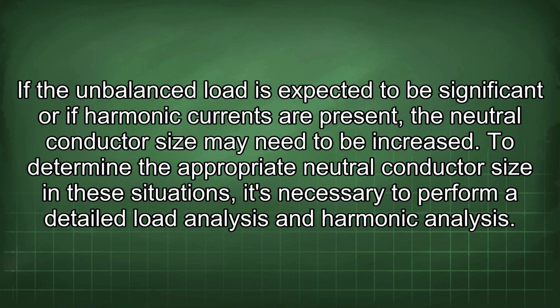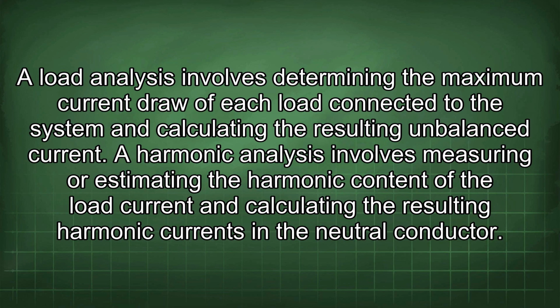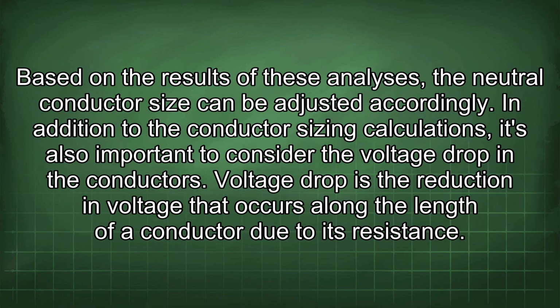To determine the appropriate neutral conductor size in these situations, it's necessary to perform a detailed load analysis and harmonic analysis. A load analysis involves determining the maximum current draw of each load connected to the system and calculating the resulting unbalanced current. A harmonic analysis involves measuring or estimating the harmonic content of the load current and calculating the resulting harmonic currents in the neutral conductor. Based on the results of these analyses, the neutral conductor size can be adjusted accordingly.